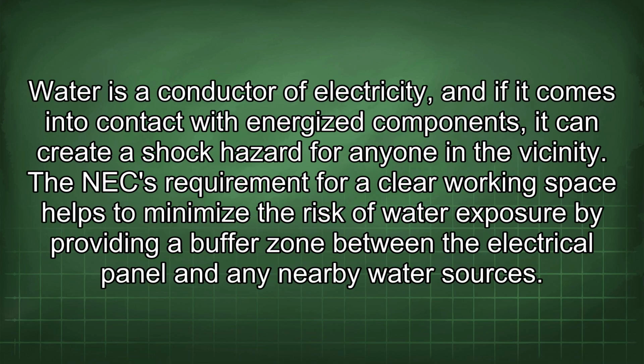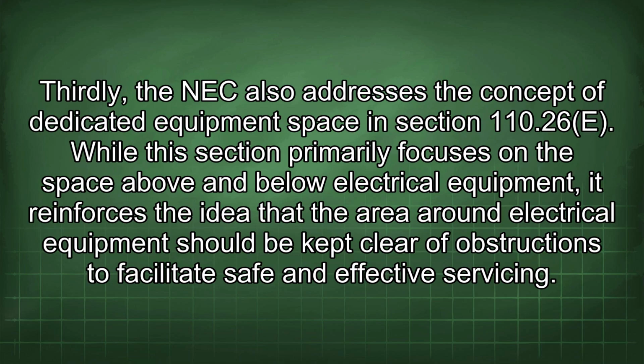Water is a conductor of electricity, and if it comes into contact with energized components, it can create a shock hazard for anyone in the vicinity. The NEC requirement for a clear working space helps to minimize the risk of water exposure by providing a buffer zone between the electrical panel and any nearby water sources. Thirdly, the NEC also addresses the concept of dedicated equipment space in Section 110.26(E). While this section primarily focuses on the space above and below electrical equipment, it reinforces the idea that the area around electrical equipment should be kept clear of obstructions to facilitate safe and effective servicing.